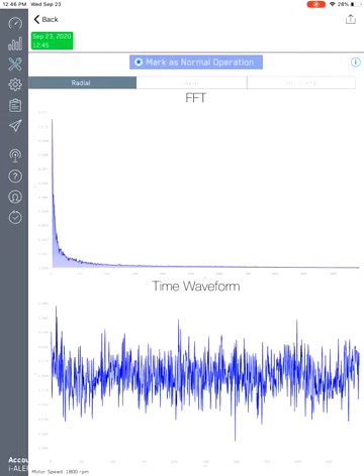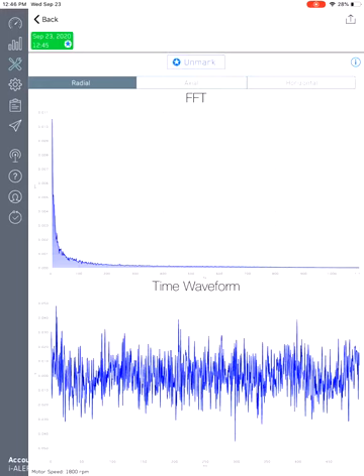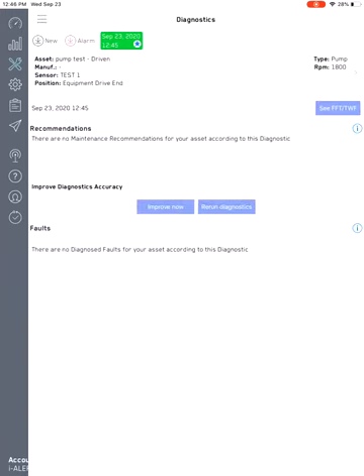If you want to make your diagnostics even more accurate, you would want to take spectrums when it's running normally and mark them as normal, like you can see over there. And once you do that, any alarm spectrums that will be coming from this particular asset will have something to refer to when it's normally running as well. So those are the things that we recommend for you guys to implement when you register these sensors to get the best out of the diagnostics, as well as to get the most accurate result when it comes to diagnostics.